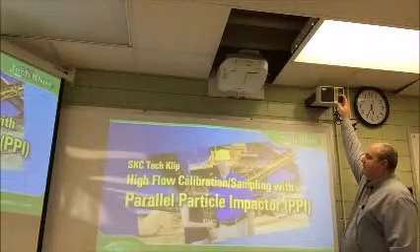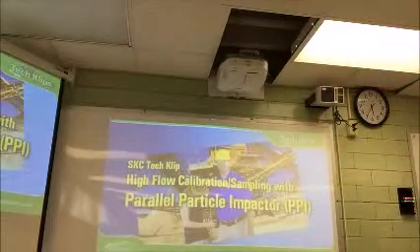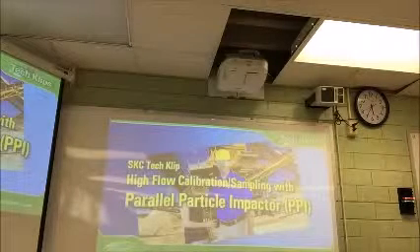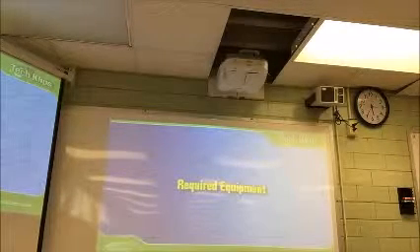Welcome to SKC Tech Klips. Today, we'll show you how to calibrate a sample pump for high-flow sampling with the SKC Parallel Particle Impactor, or PPI. Start by assembling equipment required for calibration and sampling.